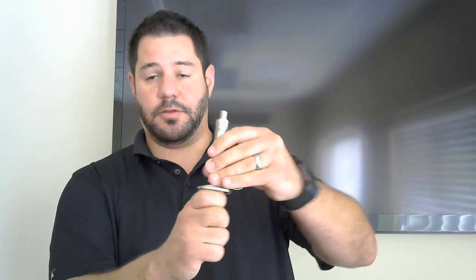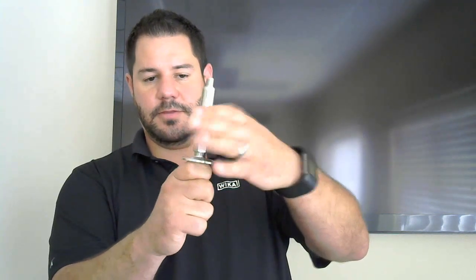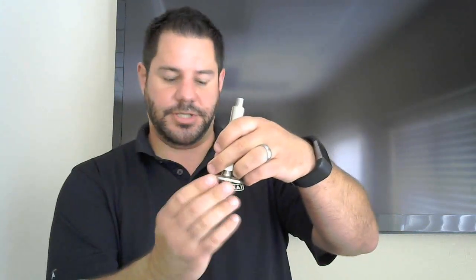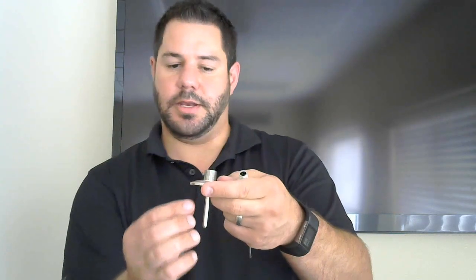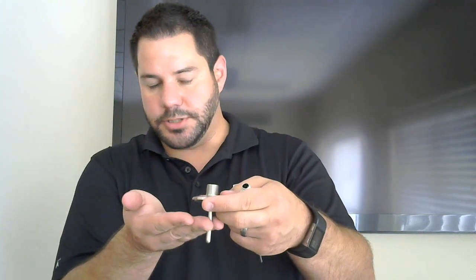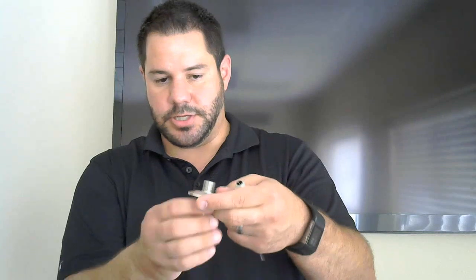The really nice thing about these too is when a customer switches to these, once they put these in, anything from that 3/4 inch to 4-inch size range uses the exact same RTD size. All we do is adjust how the thermo well sits in the tri-clamp—if you've got a very small line, we'll adjust it up for you, and if it's larger, we'll adjust it down. This makes it nice that you can have just one device sitting on your shelf. As the maintenance person, you're not searching around for the right RTD—you just pick up one of these, bring it back out, put it back in your system, and it's ready to go.